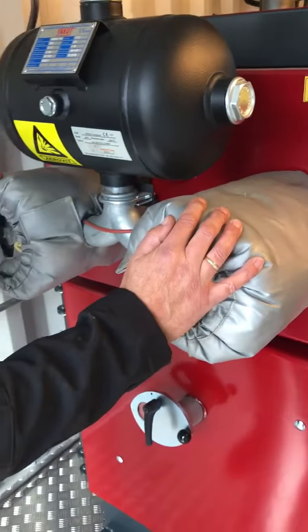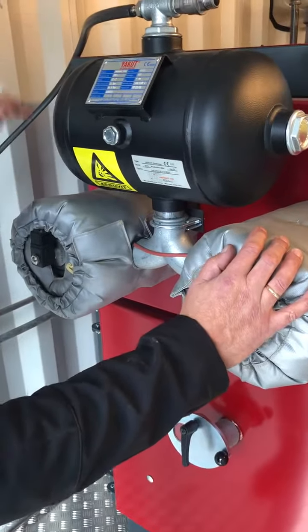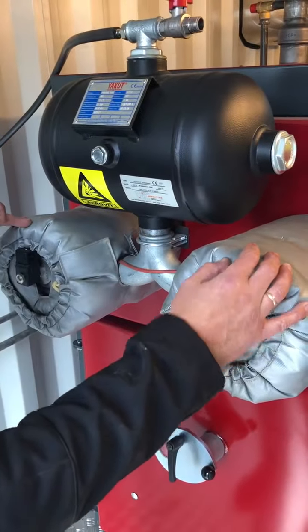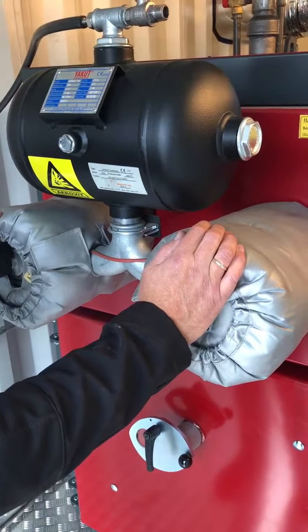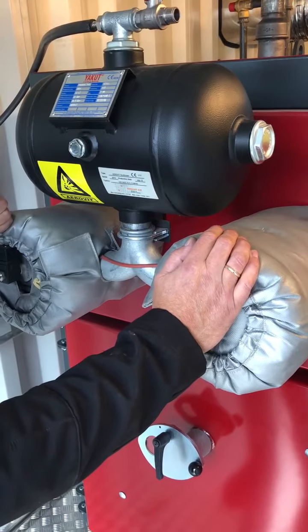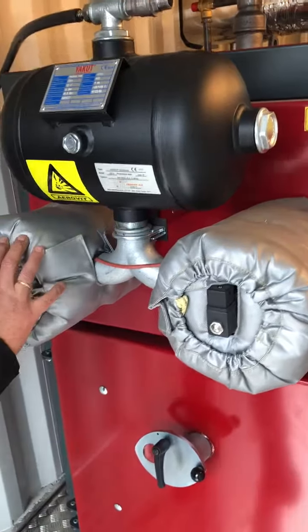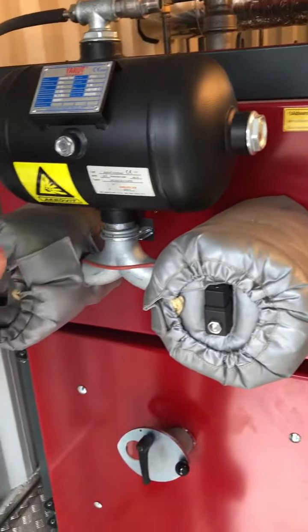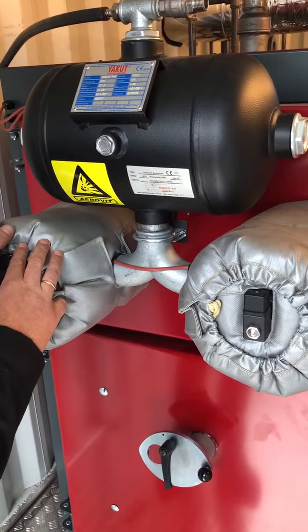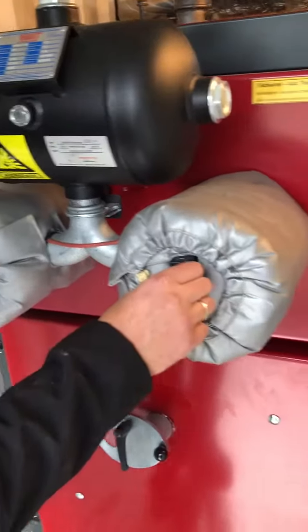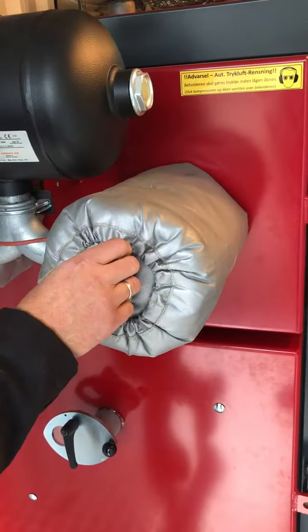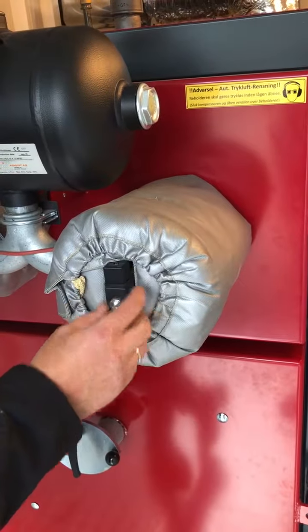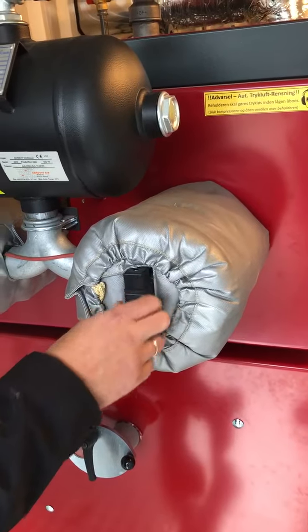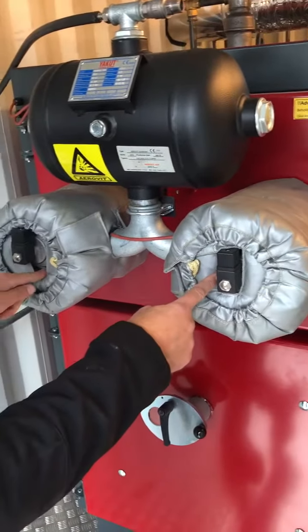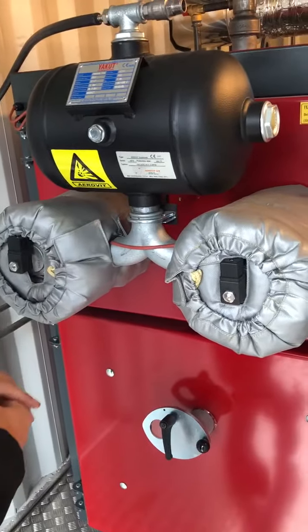Here you have the heat exchanger cleaning. It's a blast by air pressure, and it runs over time in the control panel, where it starts with the one valve, and then it opens the valve for 4 seconds, and it cleans on the one side. Then there go 4, 5, 6 minutes, depends on what is in the control panel. Then number 2 valve goes off. The time between is so that the compressor has time to be loaded up with air.